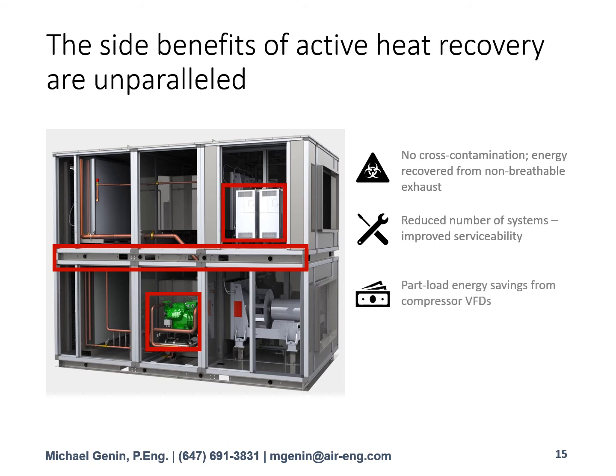The other item we briefly discussed was the part load energy savings. The efficiency of this technology is not linear, but that allows for immense part load energy savings. To further take advantage of the situations when we have part load, these units are equipped with VFD driven compressors. That not only saves energy, but also helps with the turn down ratio.